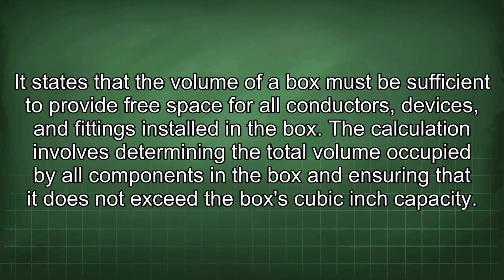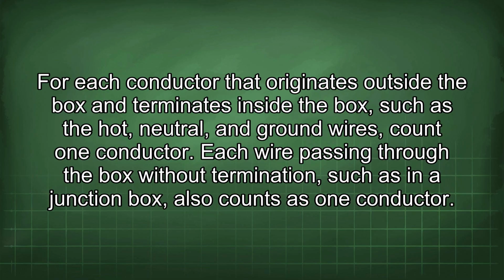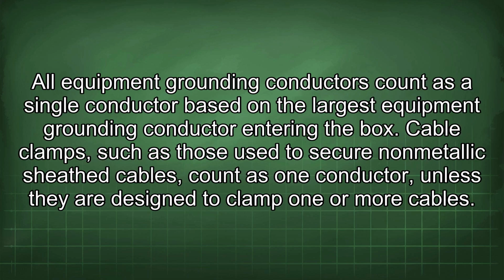The calculation involves determining the total volume occupied by all components in a box and ensuring that it does not exceed the box's cubic inch capacity. For each conductor that originates outside the box and terminates inside the box, such as the hot, neutral, and ground wires, count one conductor. Each wire passing through the box without termination, such as in a junction box, also counts as one conductor. All equipment grounding conductors count as a single conductor based on the largest equipment grounding conductor entering the box. Cable clamps, such as those used to secure non-metallic sheath cables, count as one conductor unless they are designed to clamp one or more cables.